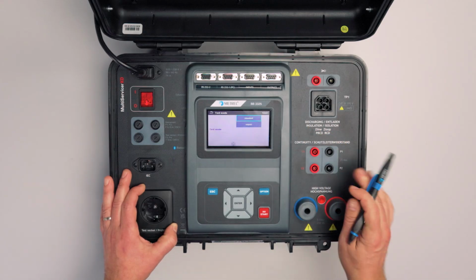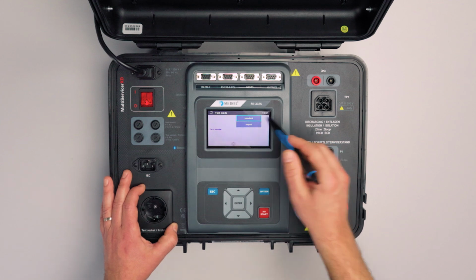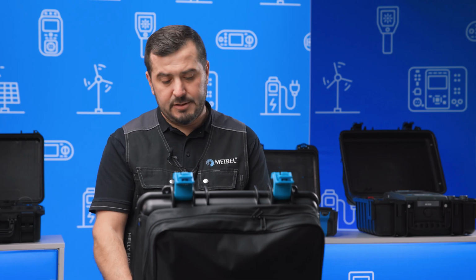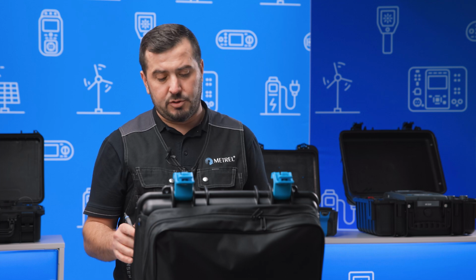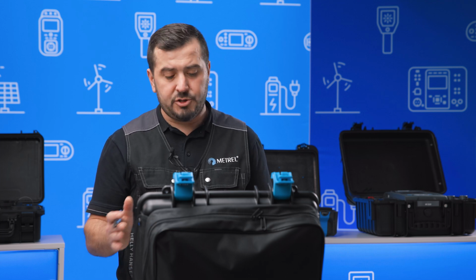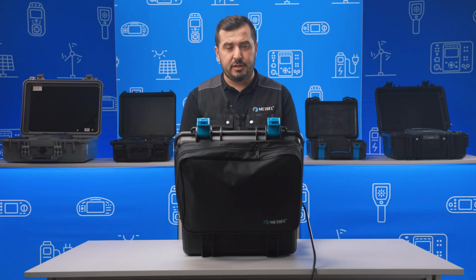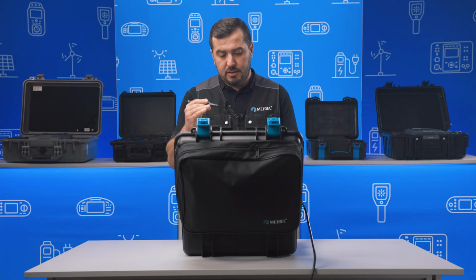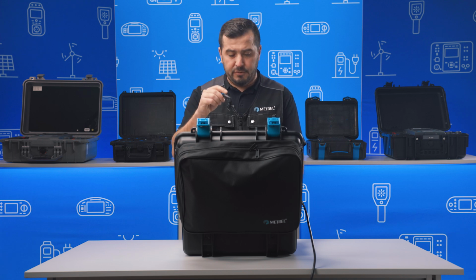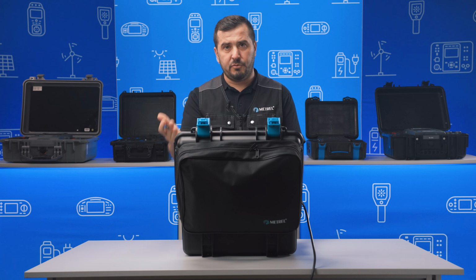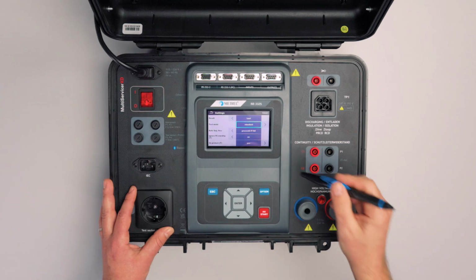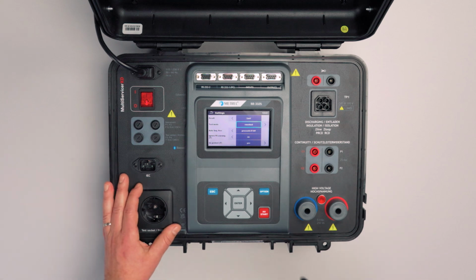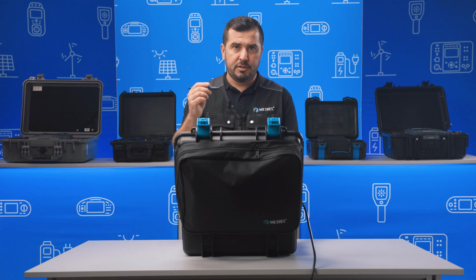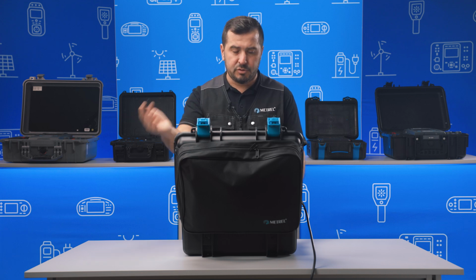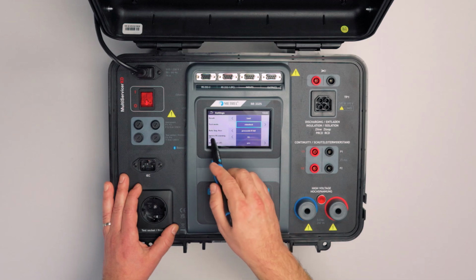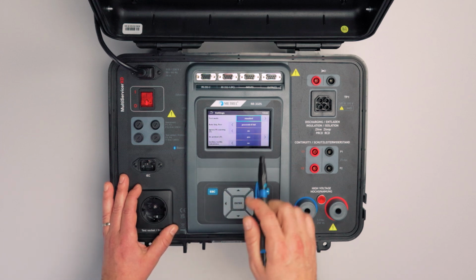Test mode, standard and expert. This has the effect on the auto sequences. So in case that the auto sequence includes also visual inspection or functional inspection, then in case of the expert mode, these inspections will be automatically filled with the tick, and the instrument will proceed to the next measuring step. In case of standard, of course, the user has to tick and check everything manually, and only then proceed to the next measuring step.